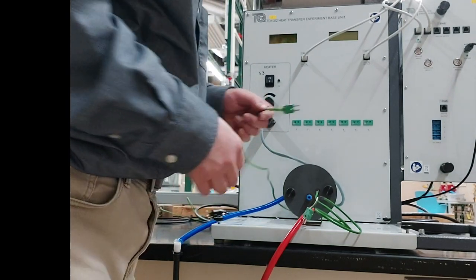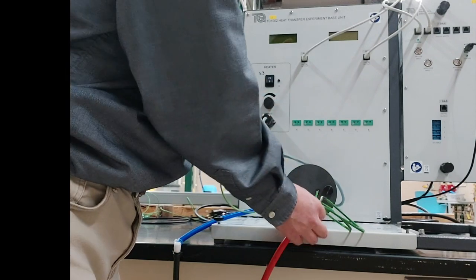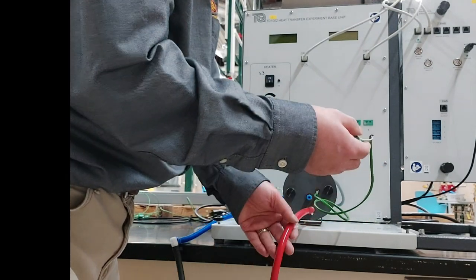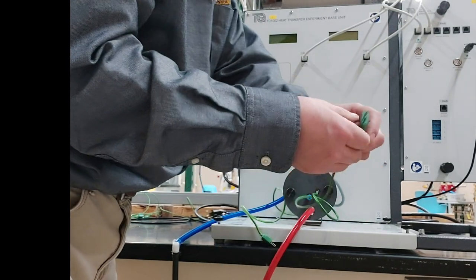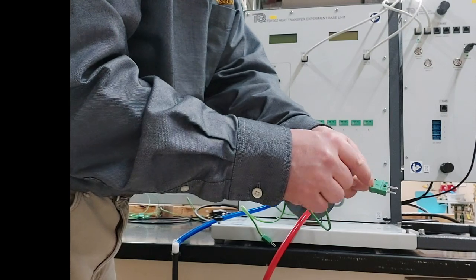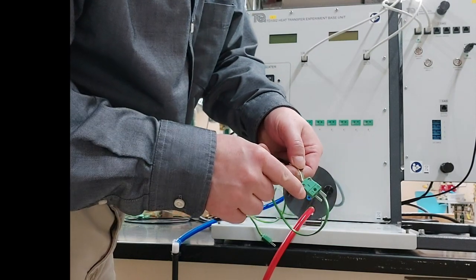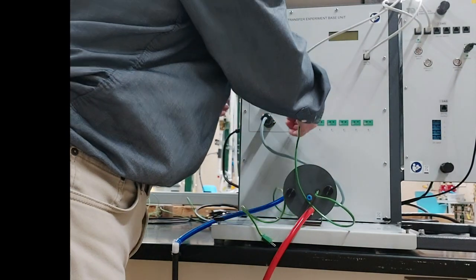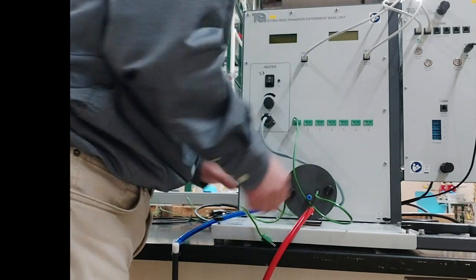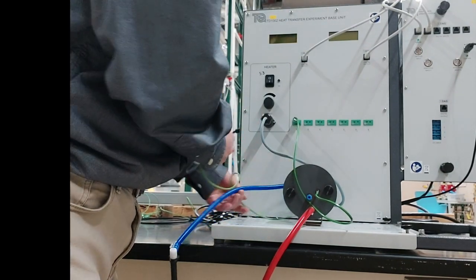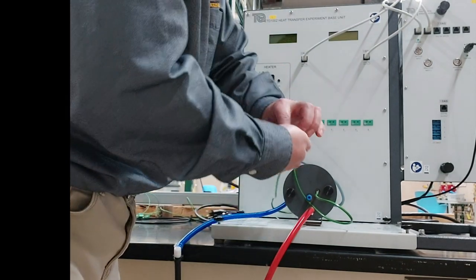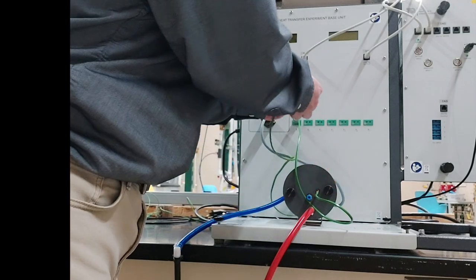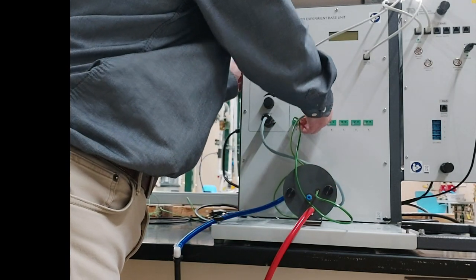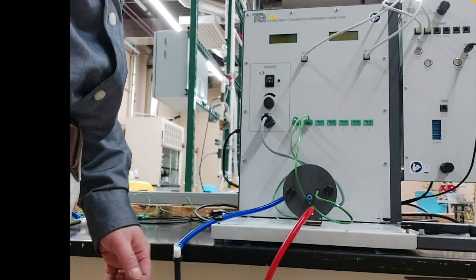You will connect 2 thermocouples from the module to the control panel. One near the red water tube is labeled 1, and this one goes to the slot T1. The other one near the blue water tube is labeled 2, and this one goes to the slot T2. And you are done with swapping the two modules.